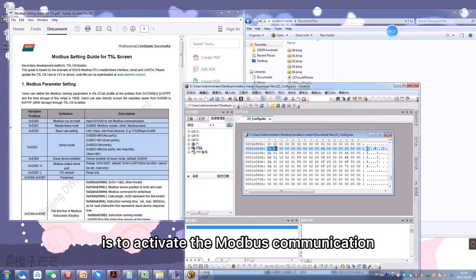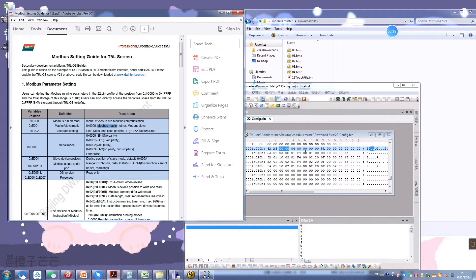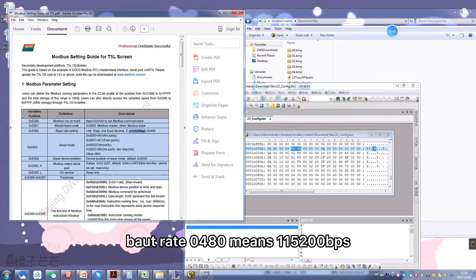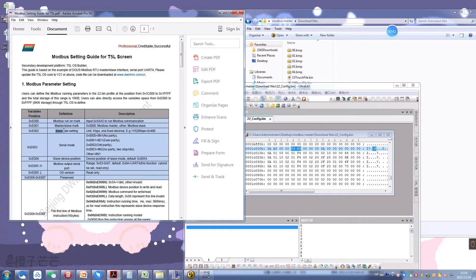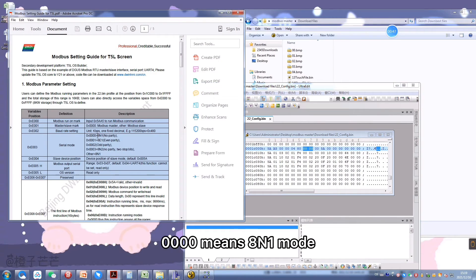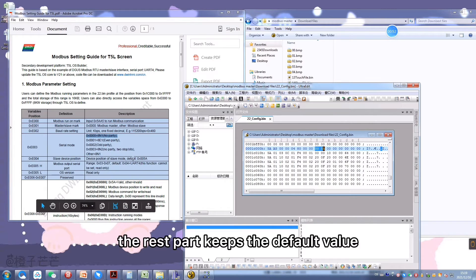0x5885 is to activate the Modbus communication. 0x4000 means activating the master mode. Baud rate 0x0480 is for 115,200. Set the serial mode: 0x0000 means 8N1 mode. Then set the address of the slave. The rest of the configuration keeps the default value.